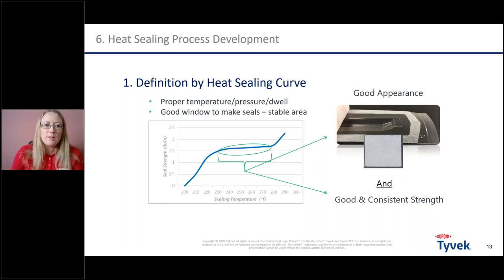You can measure seal strength, for example using ASTM F88 as a test method. Then you analyze that together with visual appearance, a visual control, and examine the seal quality. This way you can find the area or range where you have good seal appearance and consistent, appropriate seal strength.